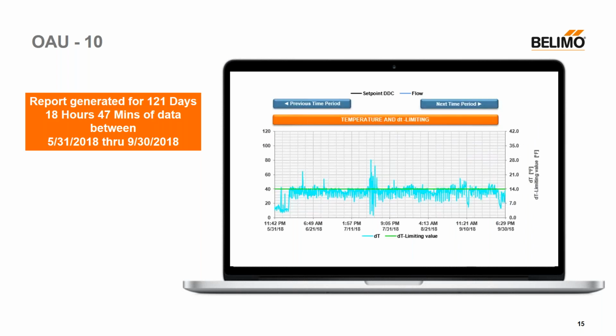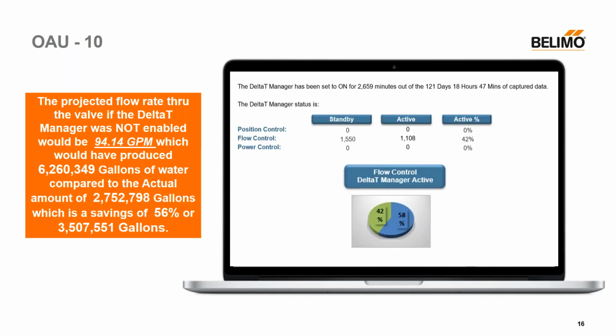We can also look at the delta T. So we can see here in this graph, we had the delta T manager set right in the middle of June. It basically got set for 14.5, and we can see what our actual delta T started to do. So again, this is 5 months of data kind of compressed into this image, but we can see what's really going on with our units and very much look at all this data. This particular unit, we can see 42% of the time the logic kicked in. That's what my little graph on the bottom is showing. And what we're saying by that is 42% of the time the valve wanted to overflow.